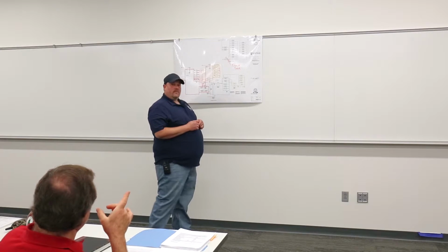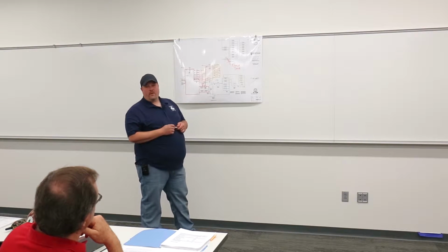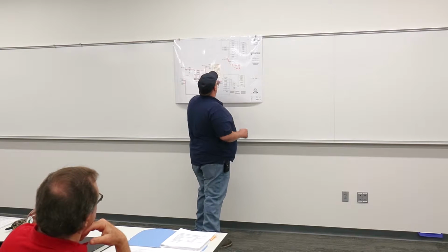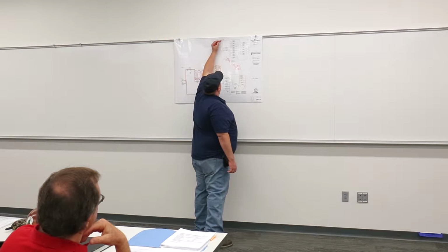There's only one condensate pump in the building? There's one condensate receiver pump, yes. Yeah, it's a duplex. Both steam lines obviously come in from the tunnel, and there's the ability to isolate those just inside the building? There are isolation valves right here as they come in from the building on the low pressure and the medium pressure.